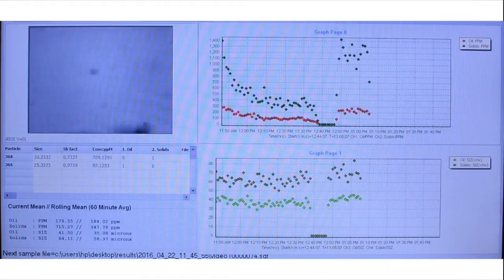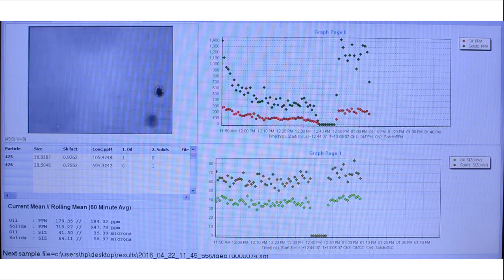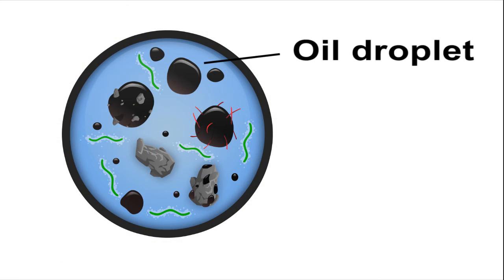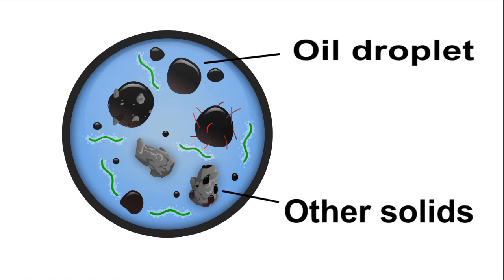Inside the particle sizer there's a thin channel that the flow goes through, and a camera across the channel which takes continuous video of the flow. Each frame then goes into the software on the computer, which looks at each image and figures out which are the dark spots — which are the oil particles — and using the shape and size it can determine what's oil and what's other solids, as well as the concentration and the size of the particles.